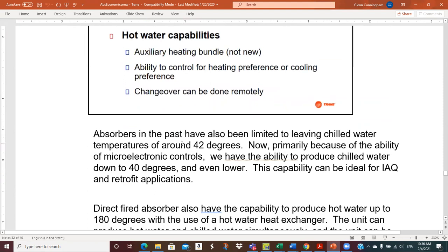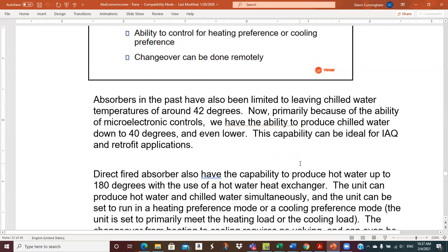Past 42 was about the limit, and now we're down to 40. And so for indoor air quality, they don't really explain that. The only thing that I can come up with is that, for example, for humidity control, sometimes we have to cool the air pretty cold to wring enough moisture out, and then we might reheat it. I think we mentioned that before. And so if you've got 40-degree chill water, you can wring more moisture out of the air, so you get better humidity control than if you only had 42-degree water. So that's what I can come up with on the indoor air quality.